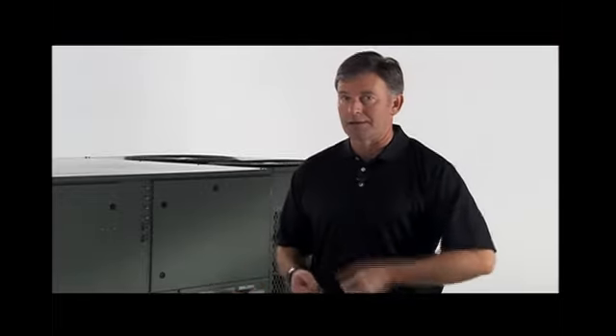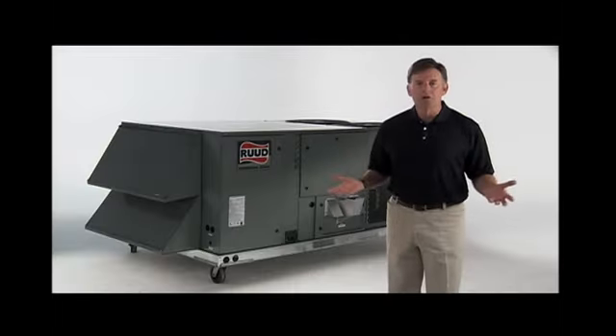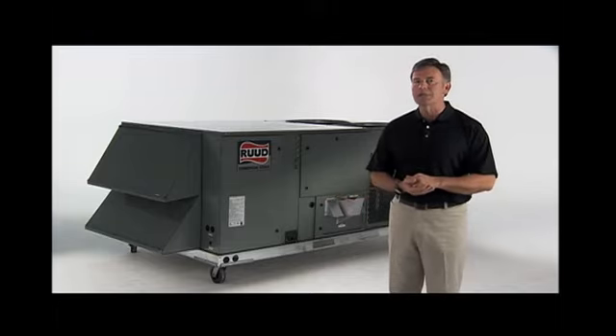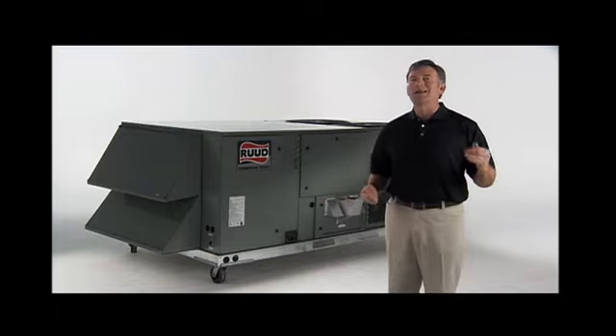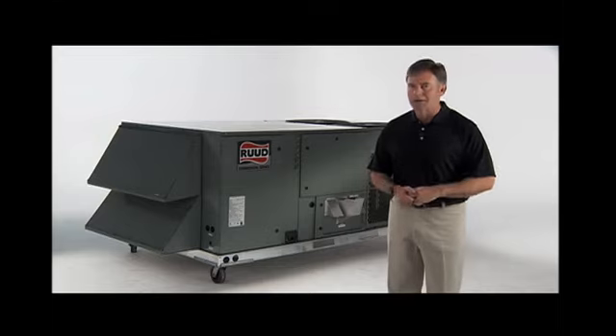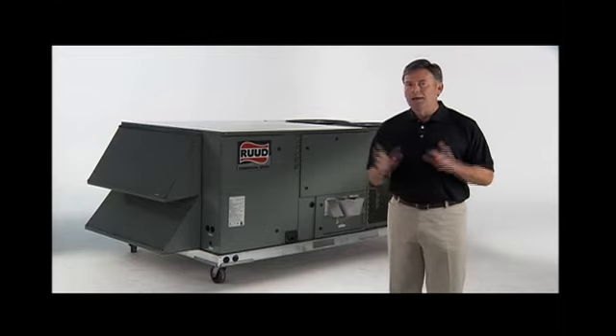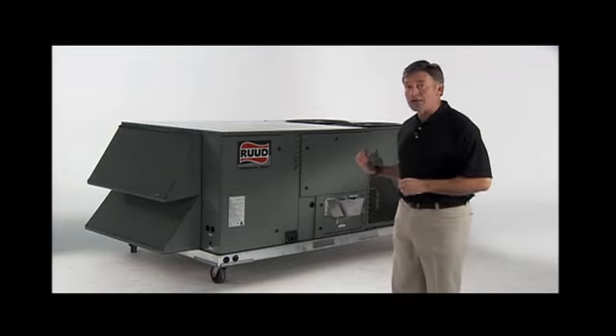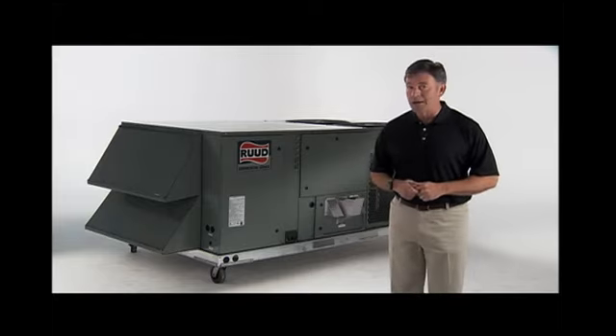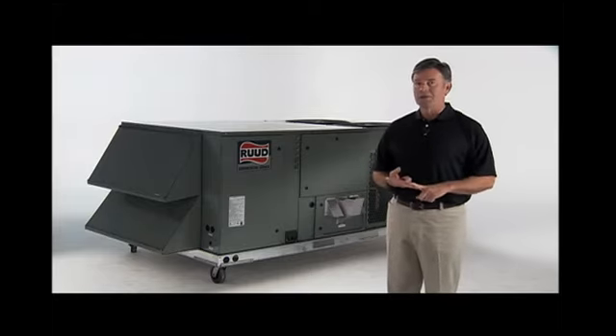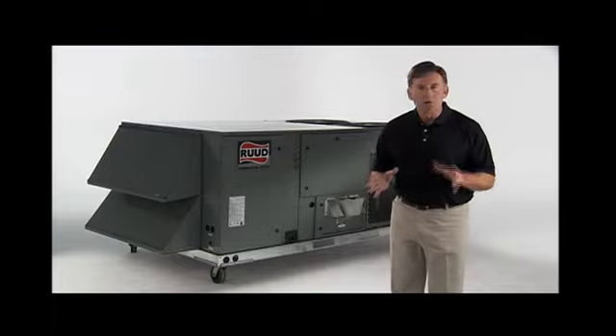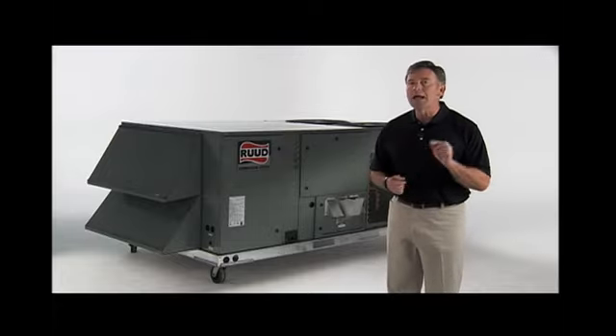Each unit is designed for either downflow or horizontal applications for job configuration flexibility. The return air compartment can also contain an economizer. Two models exist, one for downflow applications and one for horizontal applications. Each unit is pre-wired for the economizer to allow quick plug-in installation. The economizer is also available as a factory-installed option.